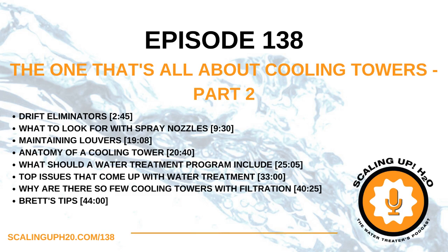What's the one thing you want to make sure everybody gets from this conversation? I think as water treaters we all know how critical it is to fully understand the makeup water quality, but it's just as important to understand the equipment that water is going to come in contact with in the cooling system. We talked about different materials of construction, galvanized, stainless steel, different types of units. So they all have different things you've got to keep in mind when treating them.